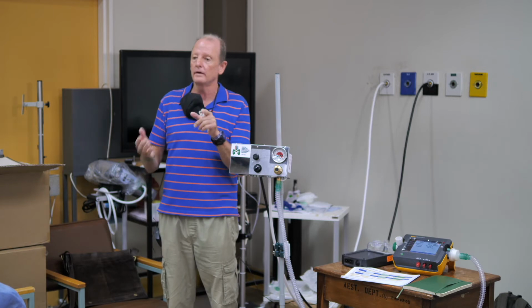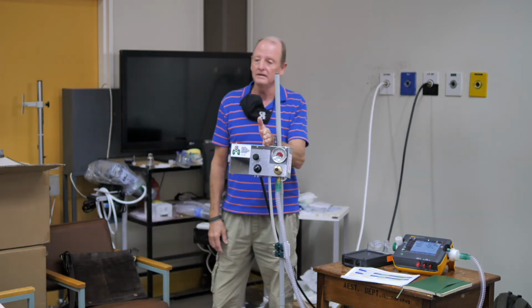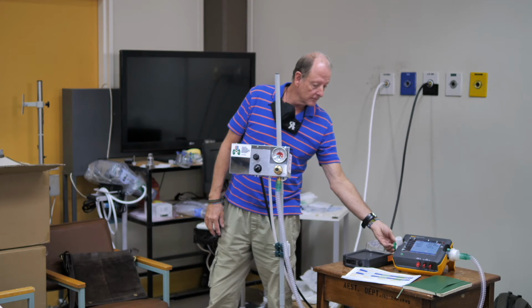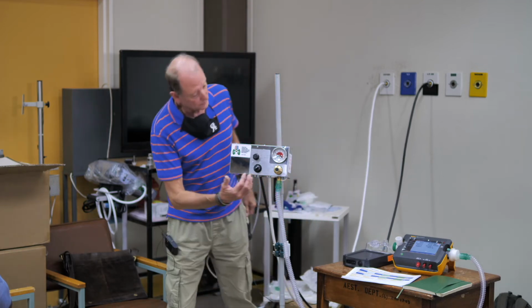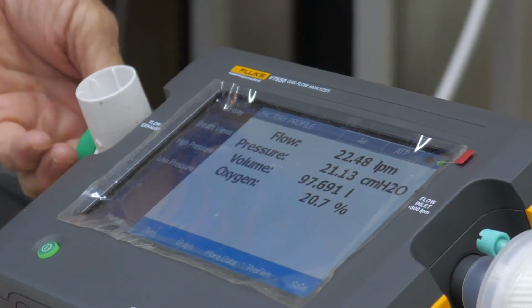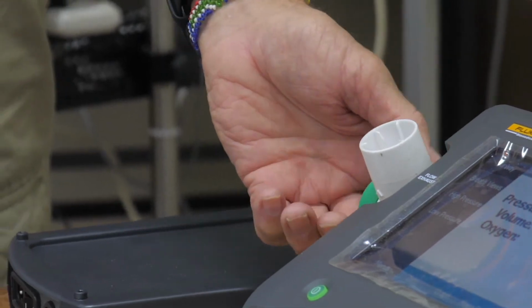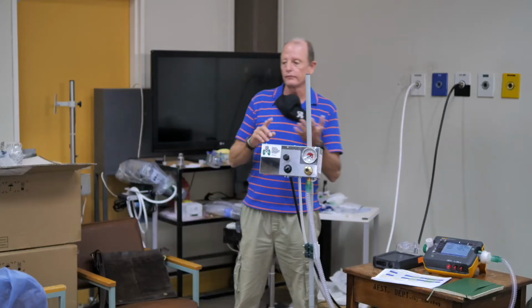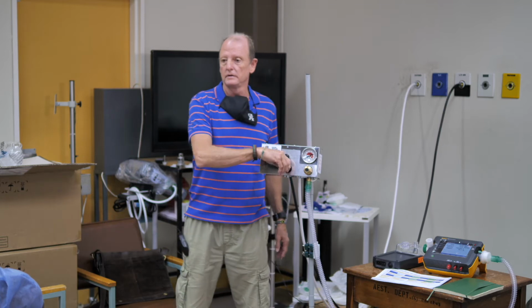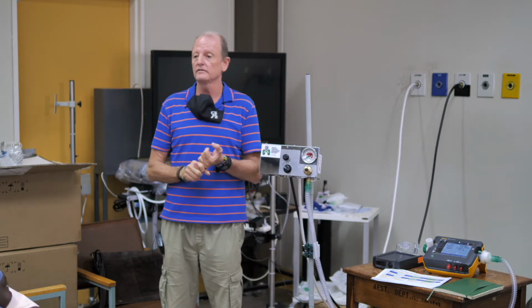Yes, we've got airway pressure. So do that on 10 and then up to roughly 20. Make sure your gauge is also reading plus or minus in those regions. All your tests for your flow rates and your percentages will be carried out at 20 liters a minute and 60 liters a minute. Nothing in between. Just check it on 20 and on 60 to see that your flow rates and your percentage calibrations are within the specs.